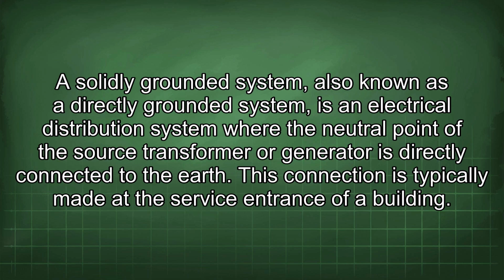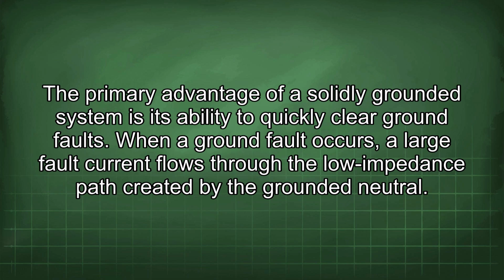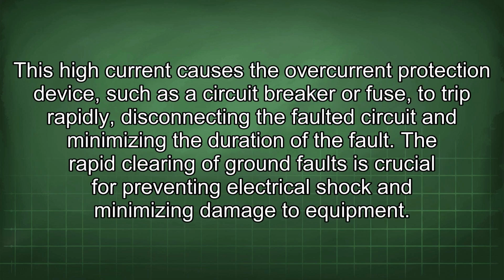A solidly grounded system, also known as a directly grounded system, is an electrical distribution system where the neutral point of the source transformer or generator is directly connected to the earth. This connection is typically made at the service entrance of a building. The primary advantage of a solidly grounded system is its ability to quickly clear ground faults. When a ground fault occurs, a large fault current flows through the low impedance path created by the grounded neutral. This high current causes the overcurrent protection device, such as a circuit breaker or fuse, to trip rapidly, disconnecting the faulted circuit and minimizing the duration of the fault. The rapid clearing of ground faults is crucial for preventing electrical shock and minimizing damage to equipment.